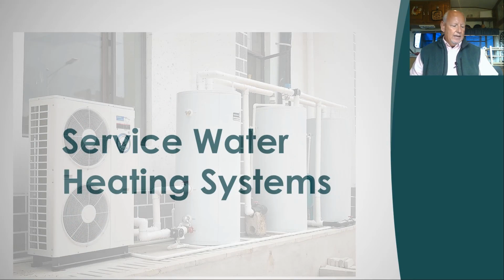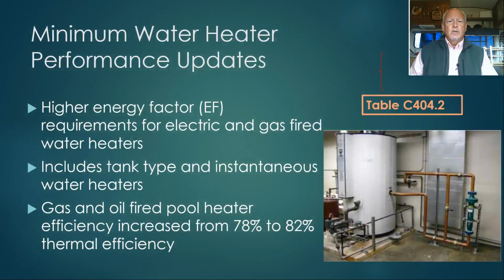So let's start off talking about the updates to service water heating systems. One thing that you're going to want to check out is updates to Table C404.2. Table C404.2 lists the minimum performance requirements for water heating equipment. There have been multiple changes increasing the energy factor requirements for electric and gas-fired water heaters. So you're going to want to review that table. Those are in line with changes that were made at the federal level through the Department of Energy, so it's consistent with federal standards and ASHRAE Standard 90.1.